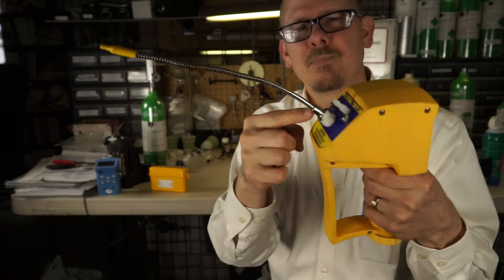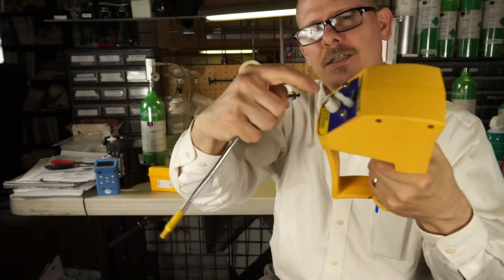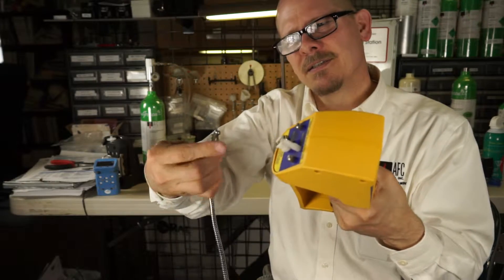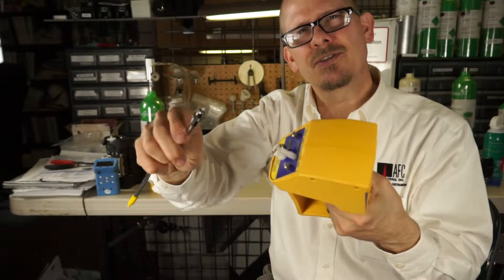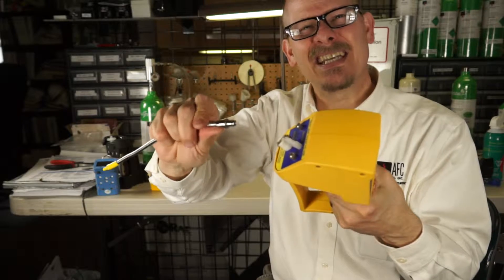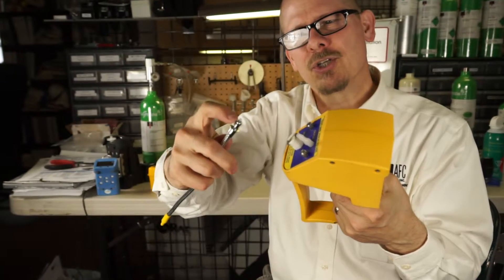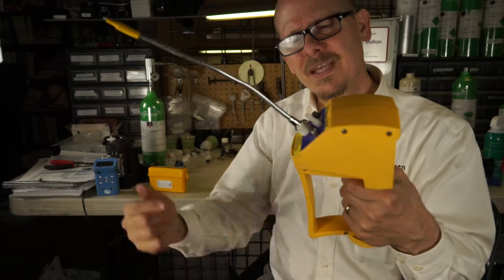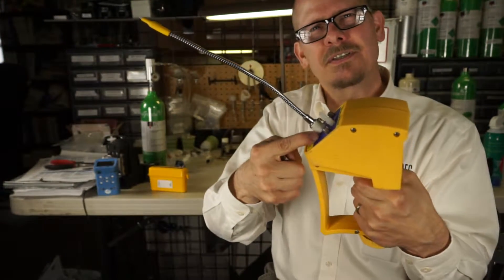On the front end we got an inlet port. It's detachable, it's got a little adapter here connector and we can just disconnect. It's Teflon line because these gases and vapors that we're dealing with these sensors are very, we call sticky, and very corrosive in some cases. So we want to make sure that the whole sample line is Teflon, non-reactive. Sample gets pulled into the instrument, goes into the sensor.